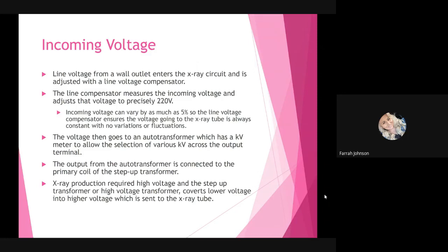So incoming voltage to our machine. So line voltage from a wall outlet enters the X-ray circuit and is adjusted with a line voltage compensator. That line compensator is going to measure the incoming voltage from the power company through the outlet and adjusts it so that the voltage is precisely 220 volts. We want a very precise voltage. We do not want it to fluctuate a lot. That can cause the circuit to short, things like that.